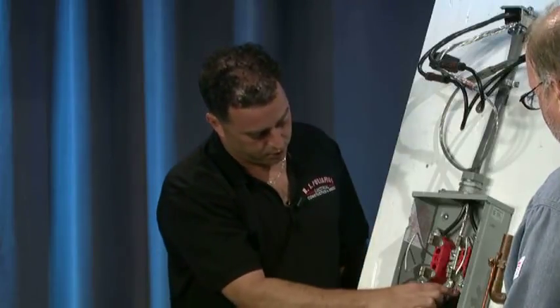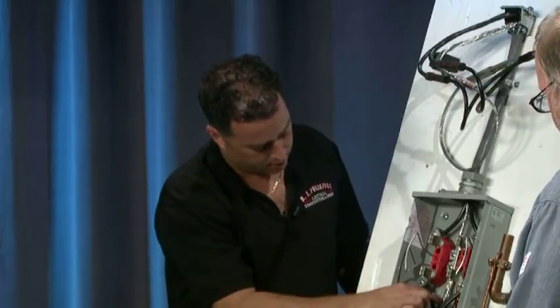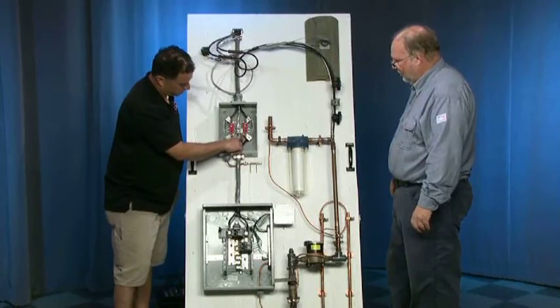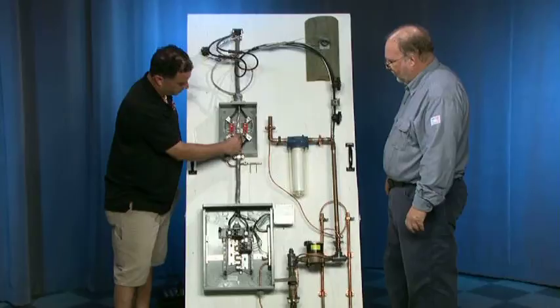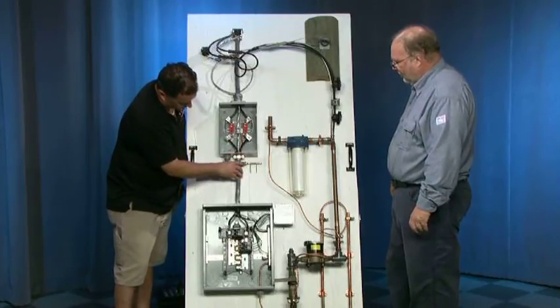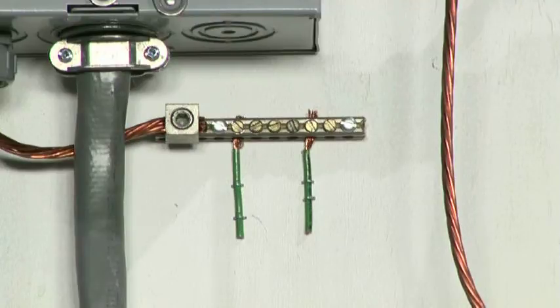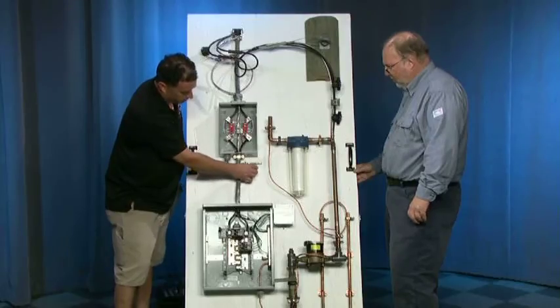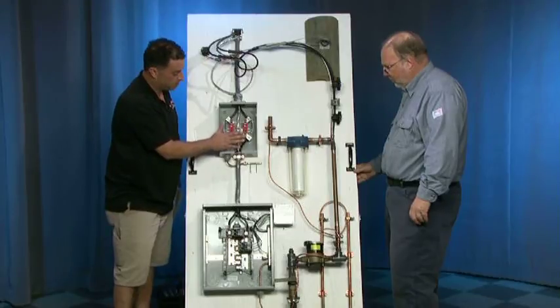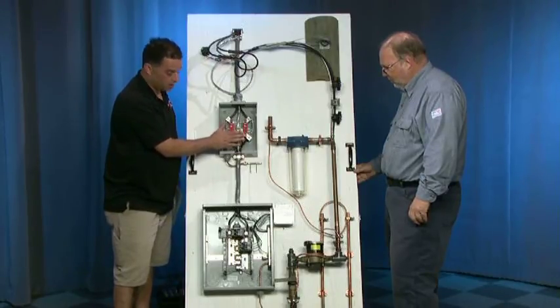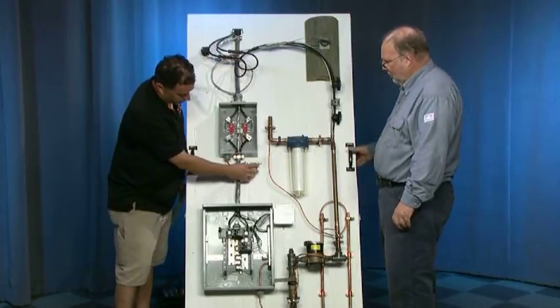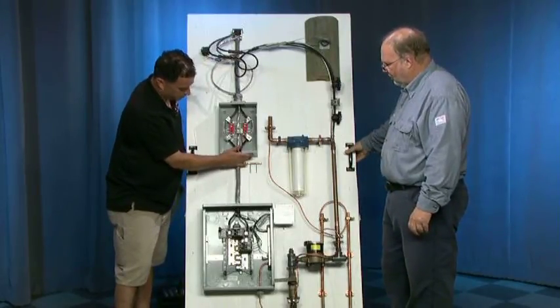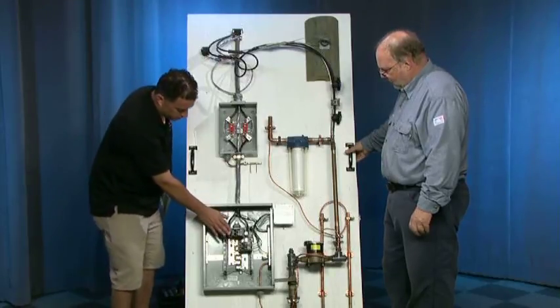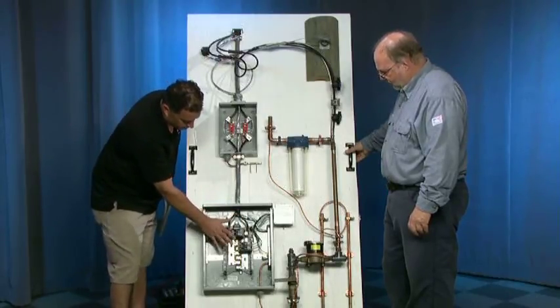Now, same thing, you have two conductors that go down to your main breaker, and you have your neutral. This also shows a ground, which is connected to the neutral with this lug. This ends up at a utility ground bar for other utilities, cable TV and telephone. They can bond to this because they're not allowed to go into this meter socket. Nobody that's not authorized can go in there. So we're required to provide this for them to connect to outside of the meter socket. So now we come into your house and you have your main breaker where this wire terminates. Under that, you would have individual branch circuit breakers that go to items in your house, lights, plugs, etc.